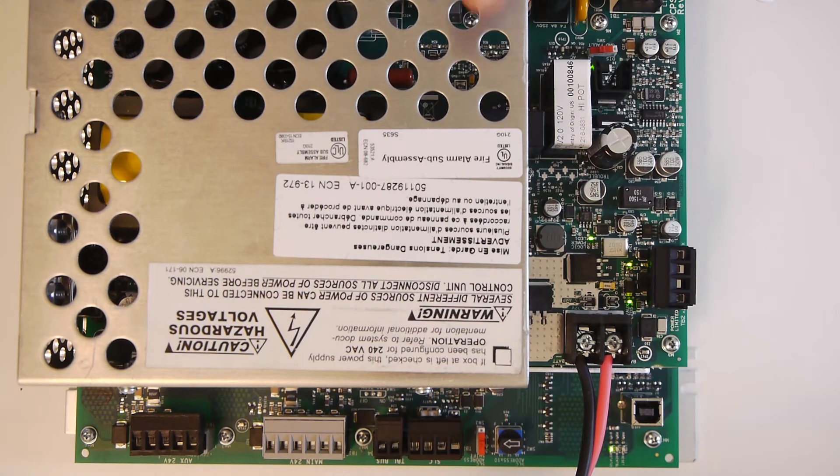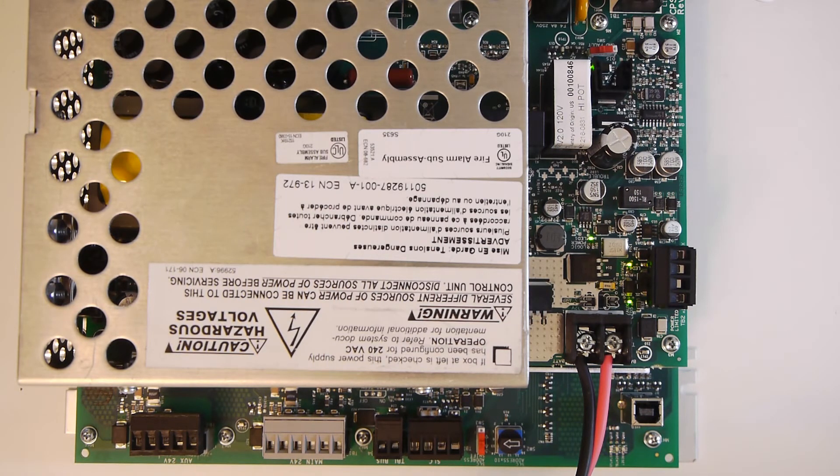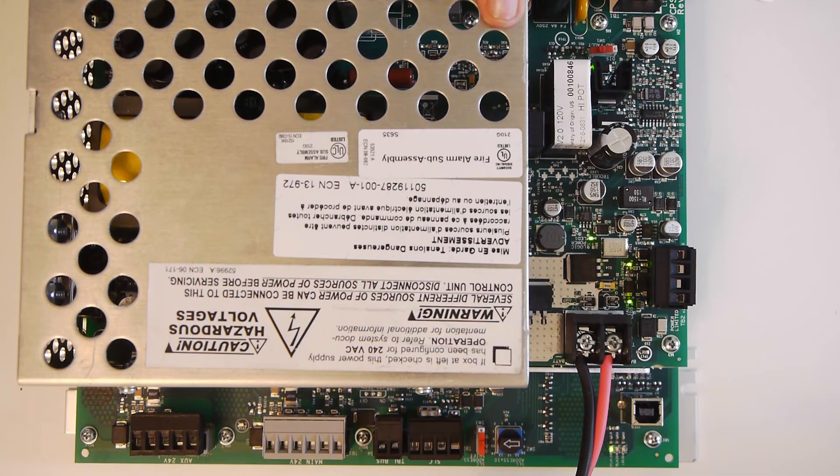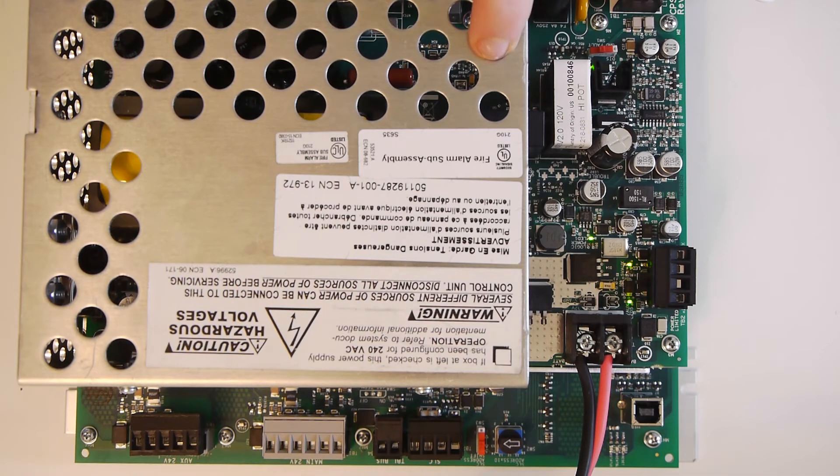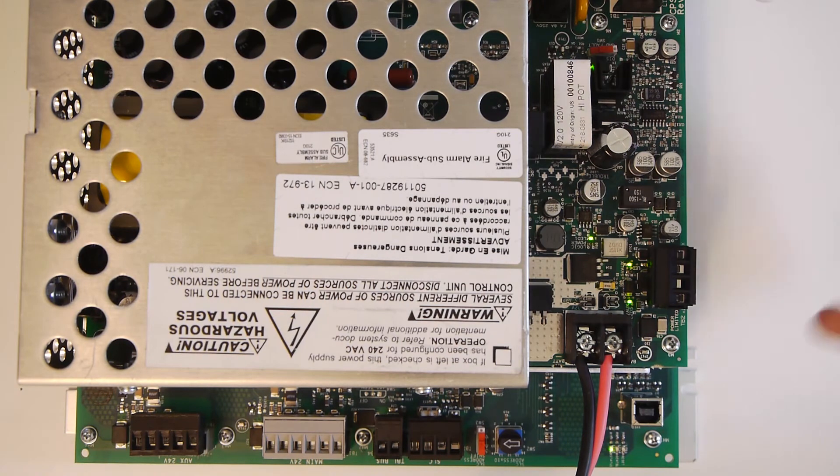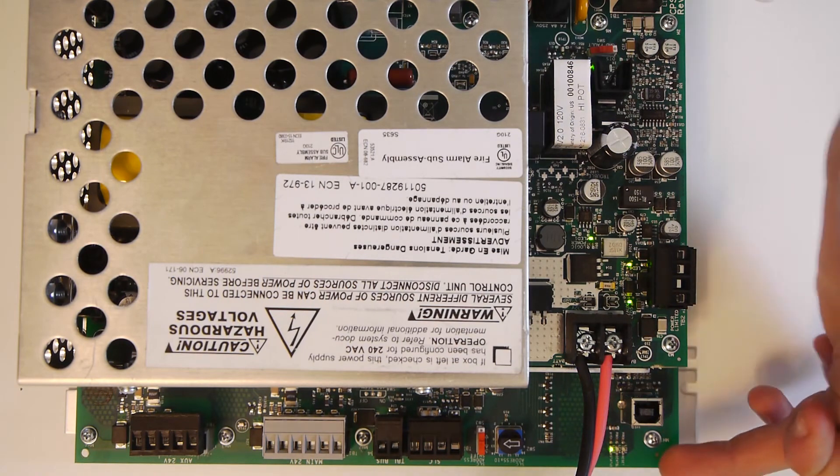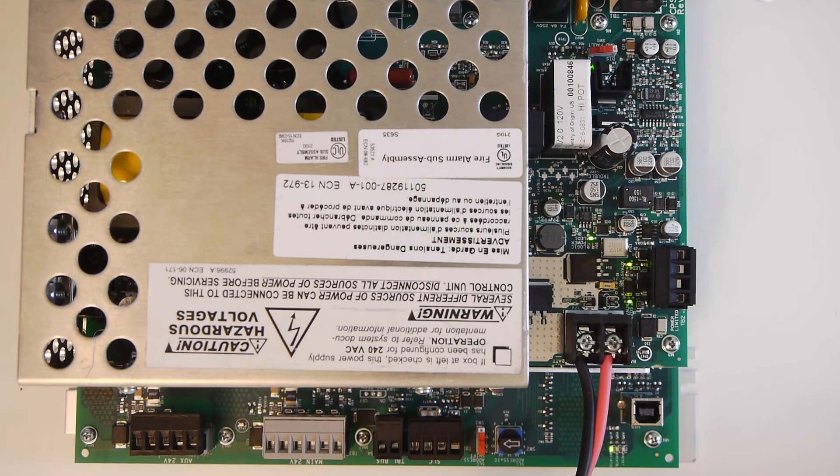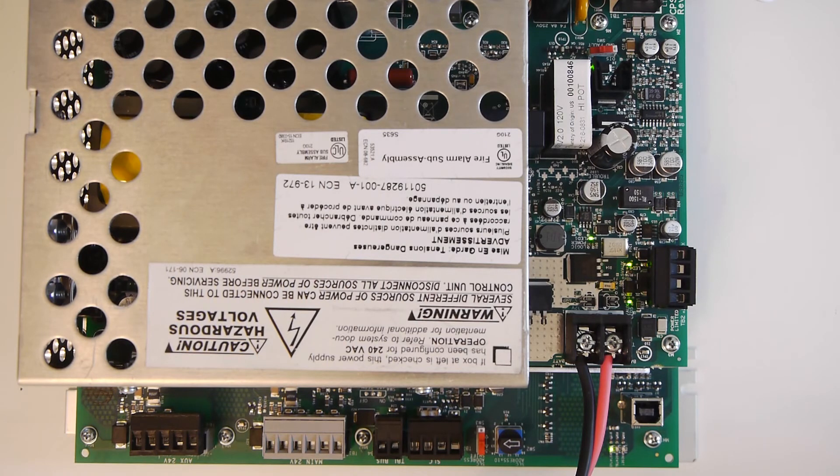Now the CPS-24 is actually a very common power supply that Notifier uses. I believe the NFS-320 and the 640 both use this power supply. I'm not 100% sure on that though. Notifier amplifiers also use this power supply, and obviously it's used here. So that's why they decided to pair it up with the AMPS board, which is basically just a way to communicate with it and give special power to the CPU.